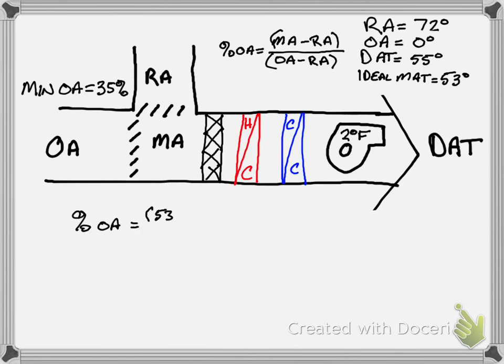And so we have to then just as we did before solve a new equation. We want to say that our 35% is our minimum outside air. And we're going to say our mixed air temperature is our unknown minus 72 over 0 minus 72.